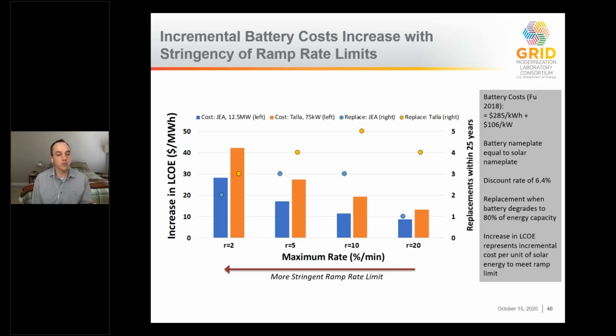And if we look at what the cost would be per megawatt hour of solar generation, we estimated that using the battery to do the smoothing function would range from about $10 per megawatt hour to $40 a megawatt hour of additional costs, depending on the degree of smoothing that you're requiring. One other interesting finding from this chart is that the costs were higher when we looked at this for just this small 75 kilowatt PV system using PV data from the city of Tallahassee. So that's what's shown in the orange bars. And that's relative to the blue bars, which are a 12.5 megawatt PV system that was located in Jacksonville.